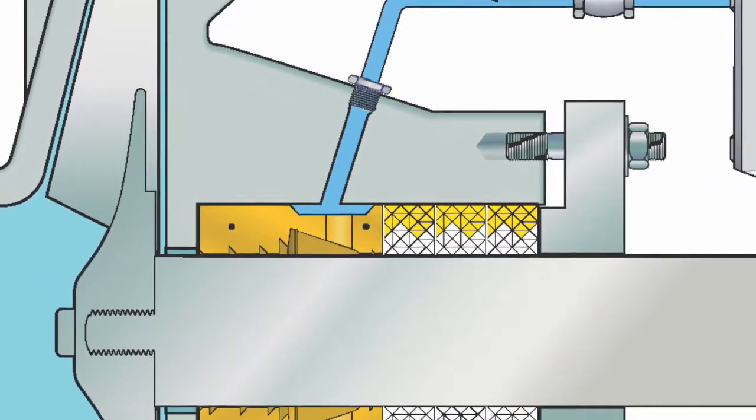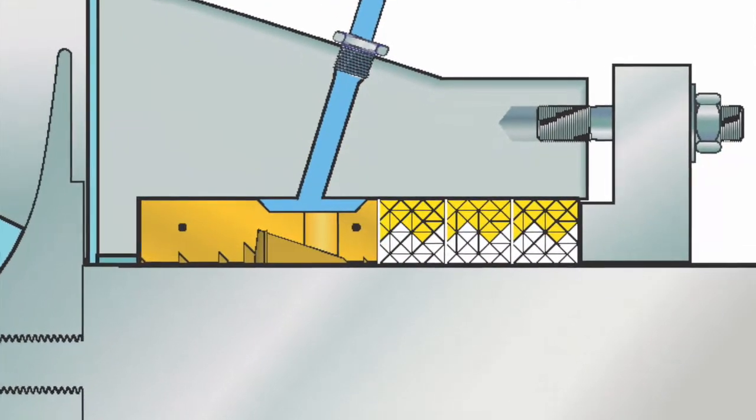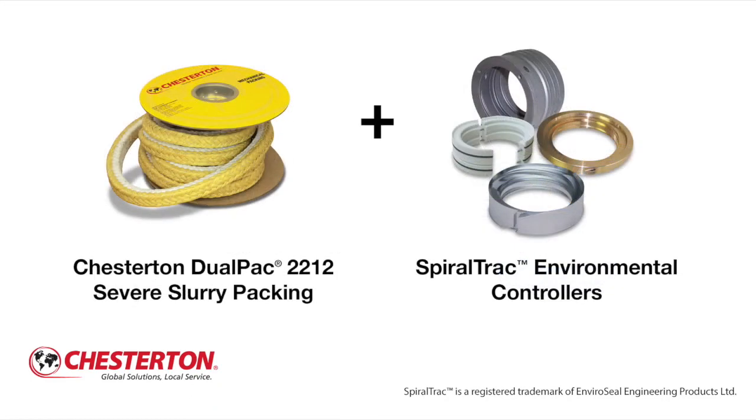The ability to remove particulate from the stuffing box is what differentiates SpiralTrac from plain restriction bushings on the market today. This is an excellent upgraded solution when five sealing rings have previously been used. The three packing rings are oriented with the white meta aramid fiber contacting the shaft. SpiralTrac enables reduced flush water usage, less packing used, and faster, easier repacks. This total sealing solution is proven to increase packing and equipment service life while dramatically reducing flush rates.